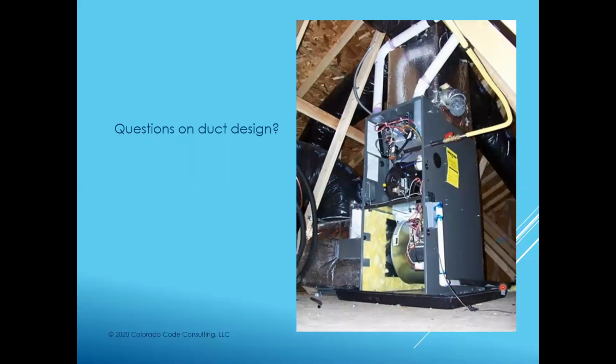Water freezes when it gets cold. They were having a heck of a time with these condensate drains and the furnaces themselves freezing. So I walked in and was doing this inspection, and they had added this piece right here. This is a supply air duct. And they're like, well, Gil, we're not done. We're going to actually extend it down so it actually heats this pipe.